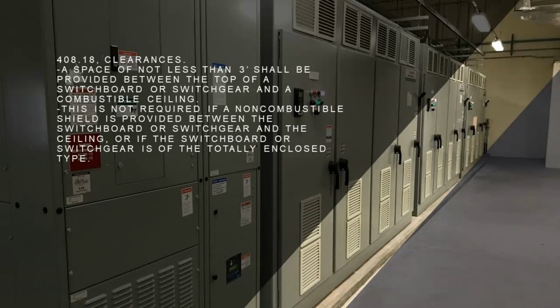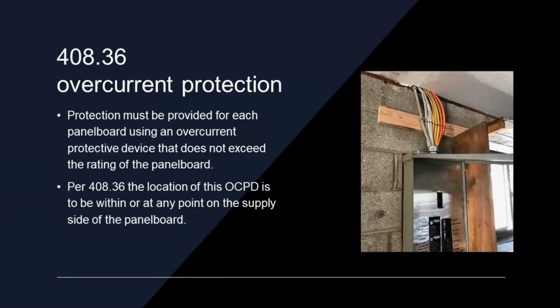I haven't seen any AC type that are open in the top, but I'm sure they exist. Just because I haven't seen them doesn't mean they don't exist. All right, 408.36, overcurrent protection. Protection must be provided for each panel board using an overcurrent protective device that does not exceed the rating of the panel board.